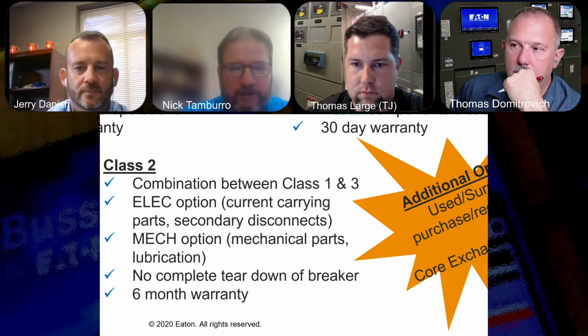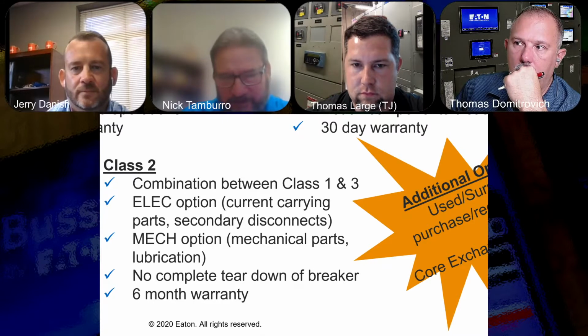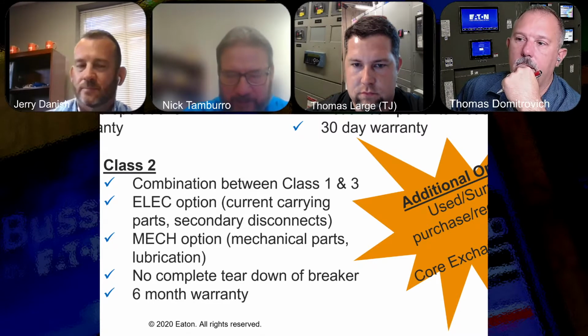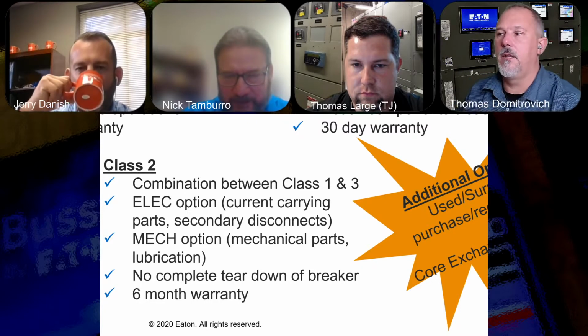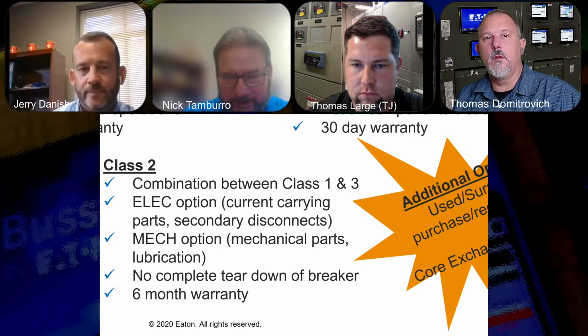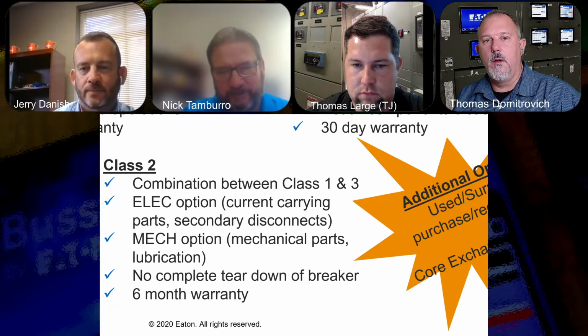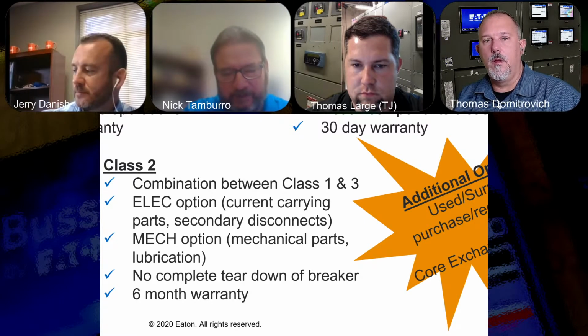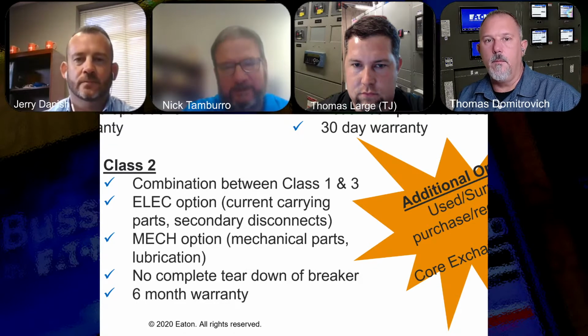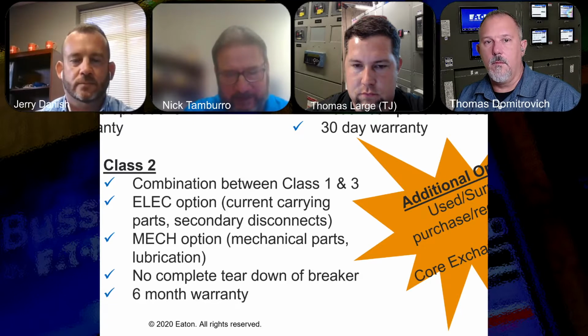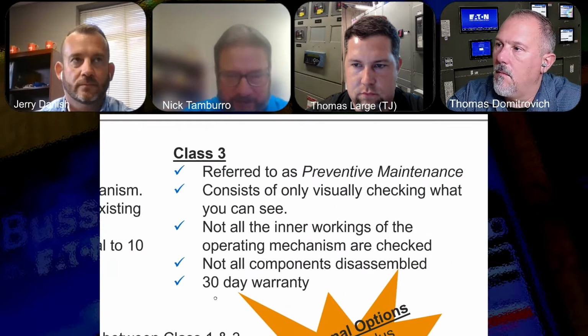So instead of doing a full Class 1, we'll offer a Class 2 MECH option focused on the operating mechanism and racking mechanism, splitting the breaker frame. The whole front of the breaker is disassembled just like a Class 1. The only difference is we don't send the steel off for plating, we just clean it in house, and when we rebuild it, we follow the same Class 1 procedures with lubrication and everything else. The rear portion of the breaker we treat as a Class 3 assembly, which is just preventative maintenance.